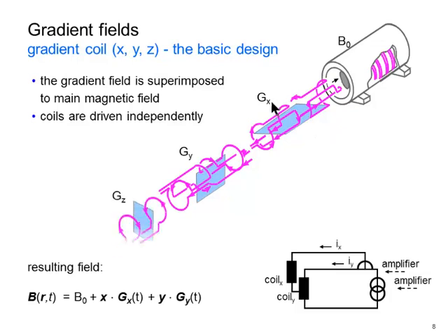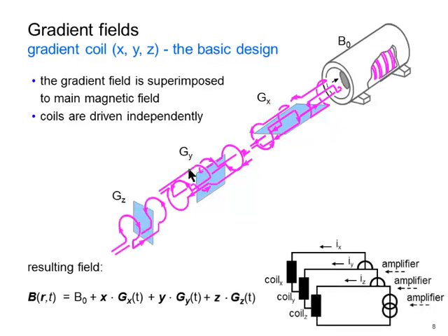If you have a look at the makeup, we are using different gradient coils for the Gx system and the Gy system. We are using saddle coils. Those are a little bit less efficient compared to the anti-Helmholtz configuration that we are using for the Gz. That means we are getting more gradient for a given unit current if we are putting it in.